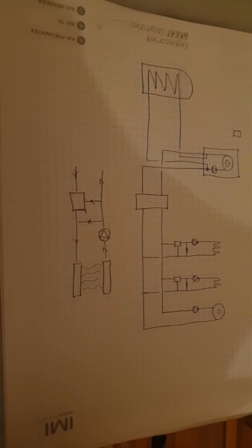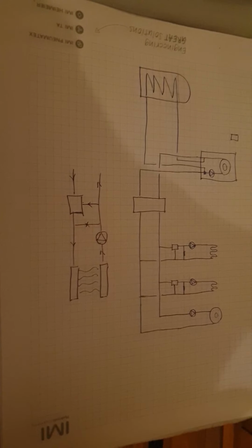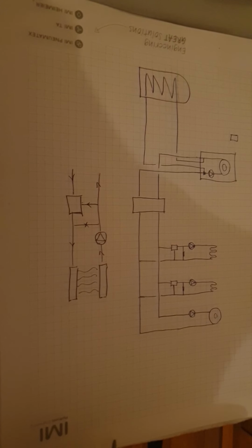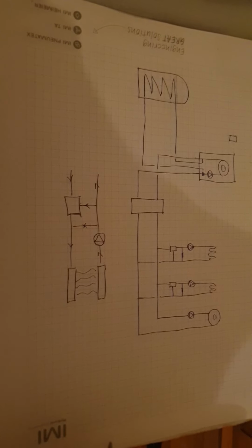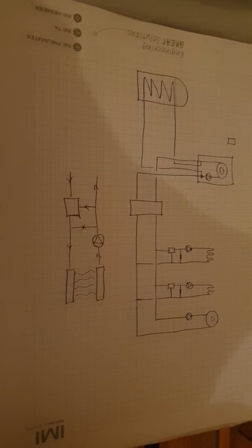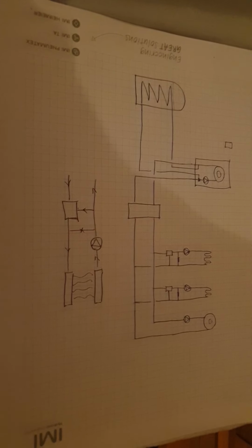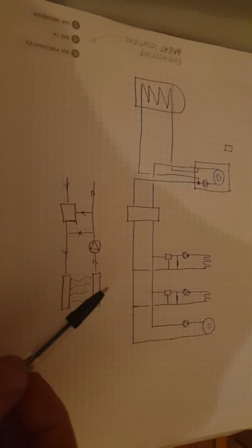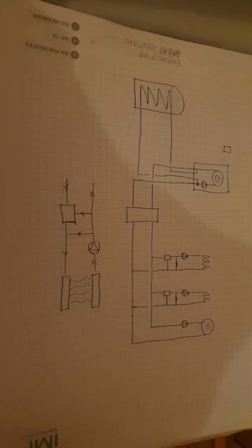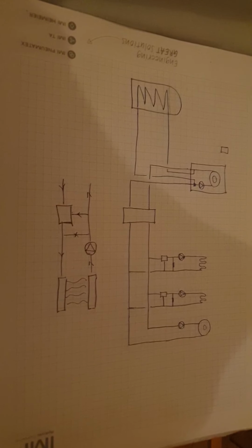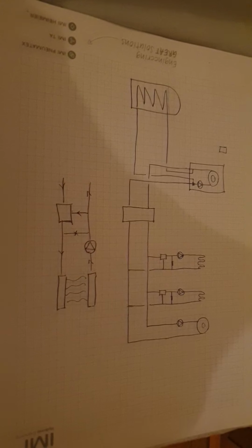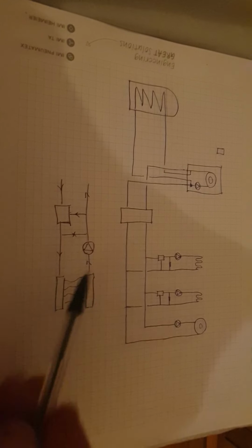I'm redrawing this out. I'm trying to rush this video out a little bit for a conversation. Putting close coupled T's in before a standard manifold just creates a short circuit. Basically, the water from the boiler pump can just rush straight through that close coupled T, and there's just nothing left to run the radiators. You might get them to function, but they're not going to be getting the same flow rate as when the valve on the underfloor is closed.